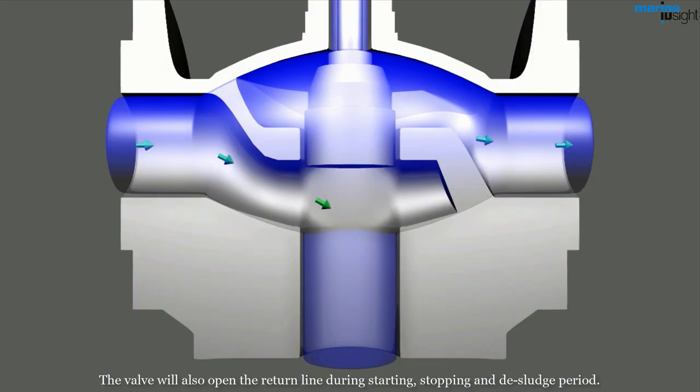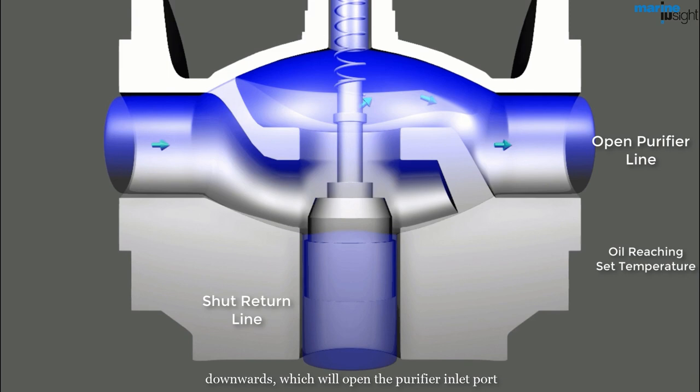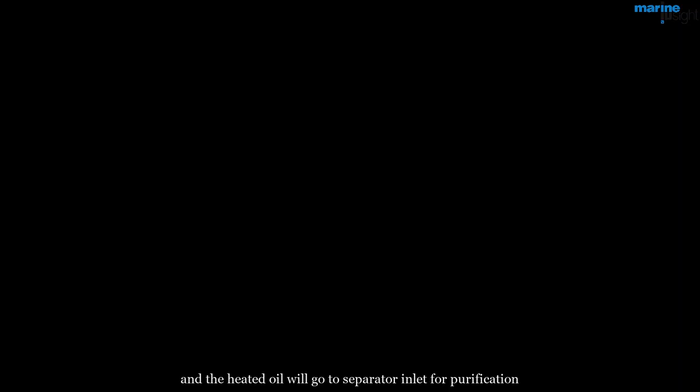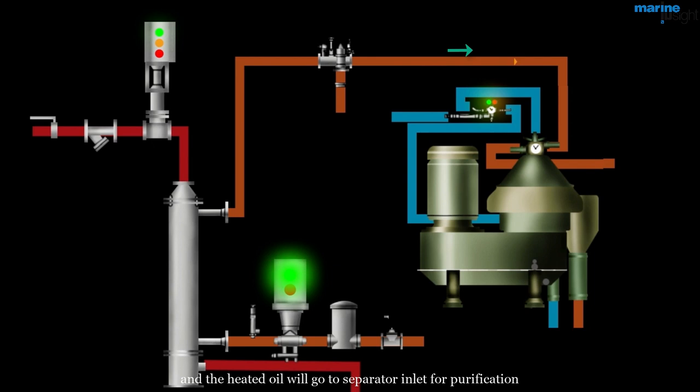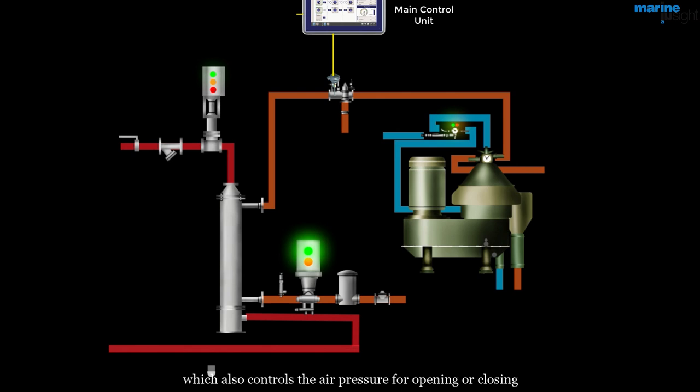The valve will also open the return line during starting, stopping, and desludge period. If the set temperature is reached, the controller will operate the valve downwards, which will open the purifier inlet port, and the heated oil will go to the separator inlet for purification. The thermosensor on this valve sends the signal to the control unit, which also controls the air pressure of the pneumatic control steam valve to reach the desired oil temperature.